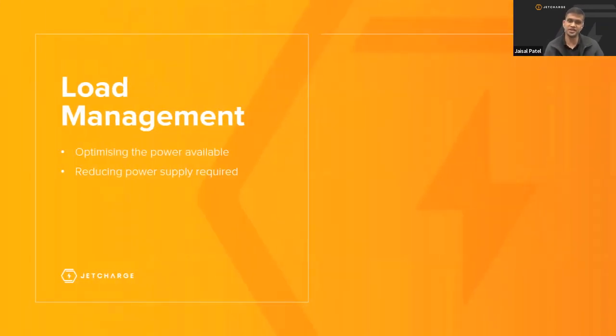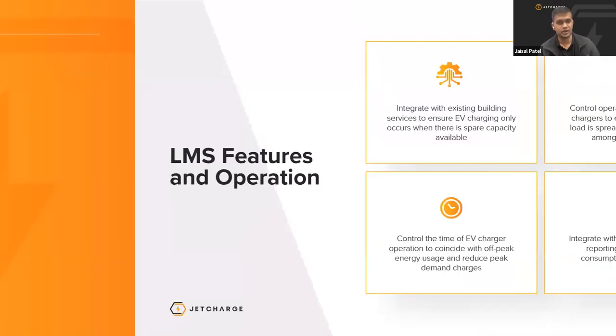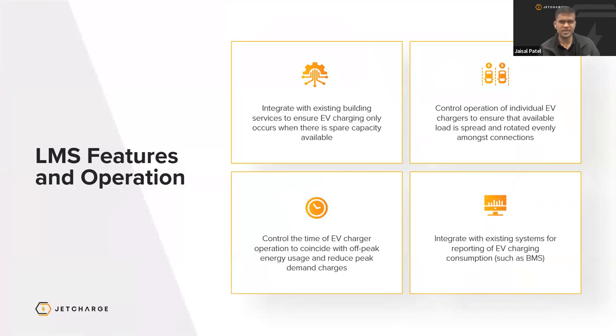Load management systems typically optimize the power that's available and reduce the power supply required to charge the EVs. Next slide. Most LMSs have different ways of operating and features, but they essentially fall under the umbrella of these four core features. They integrate with the existing building services supply to ensure EV charging only occurs when there's spare capacity available. The second feature is that they control the operation of individual EV chargers to ensure that available load is spread and rotated evenly amongst the connections.